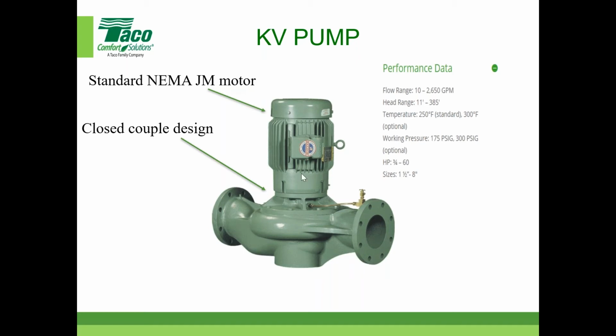Notice that these pumps only go up to 60 horsepower, so they're a lot smaller in nature. You can tell we only go up to 8-inch here, and the flow rate is like 2650. So really the range is a lot closer to the base mounted pumps, which I think go up to just over 4,000. It's kind of in that range. But the other stuff is pretty much the same: head range, temperature, working pressures, and all of that.